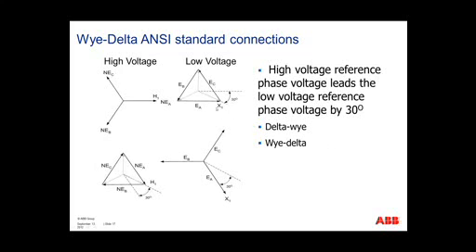Wye-Delta ANSI standard symbols. This is just showing what we've talked about previously about plotting our phasors vectorially. We can see that no matter what, if you have a Wye-Delta or a Delta-wye connected transformer, the high side will always lead the low side by 30 degrees. And that is, in turn, if you have an A-C or an A-B delta connected transformer.